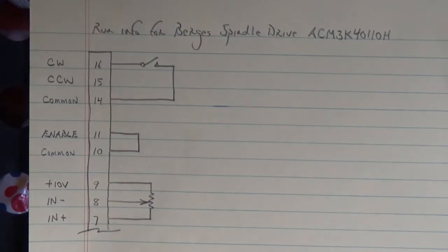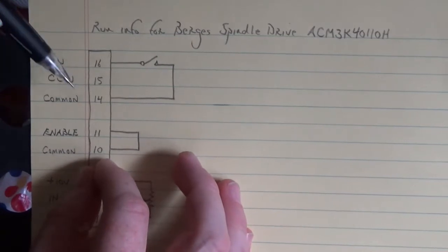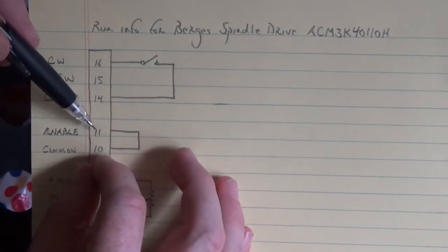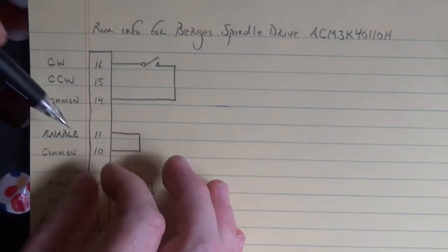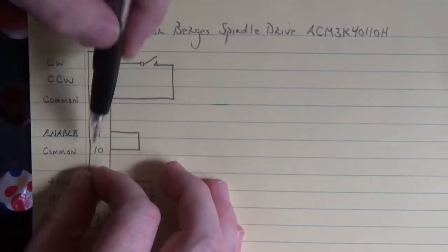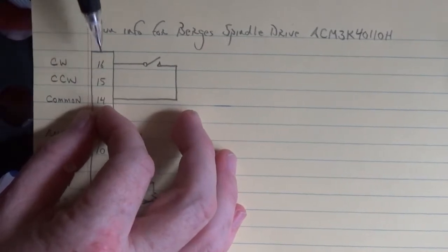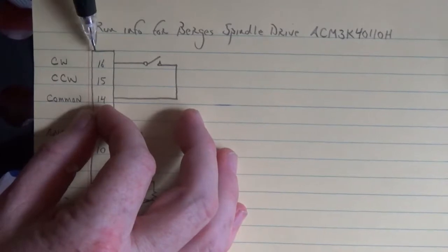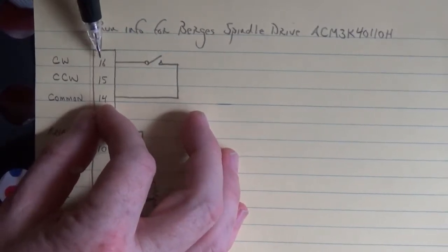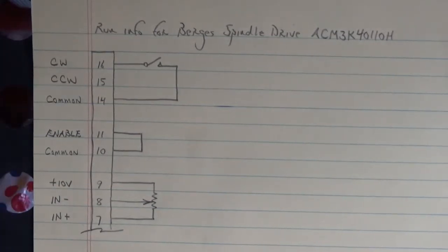I've had some Berges drives where I had to put five volts into pin 11 from an external power supply, and five volts into terminal 16 or 15 from an external supply, with the grounds connected to common 14 and common 10. To tell whether you can use a switch or need an external supply: put your black lead on terminal 10 and your red lead on terminal 11. If you see five volts, just jump it out. If you see zero volts, you need to supply an external five volts. Same for terminals 16 and 15 referenced to terminal 14.